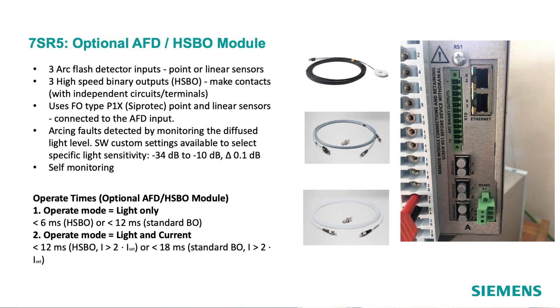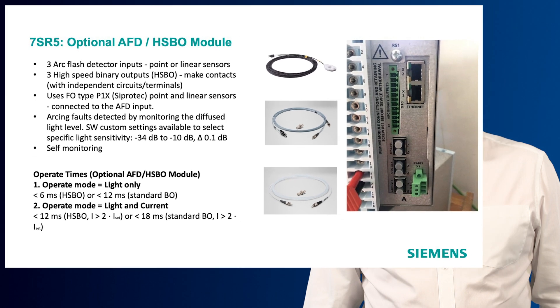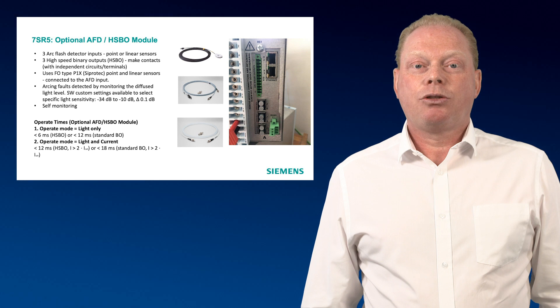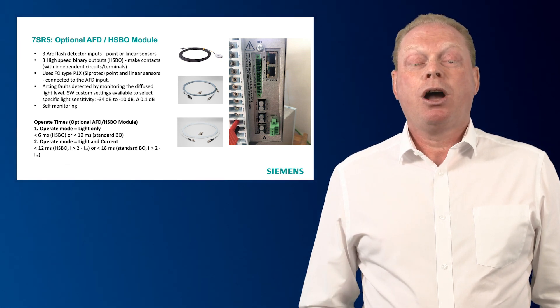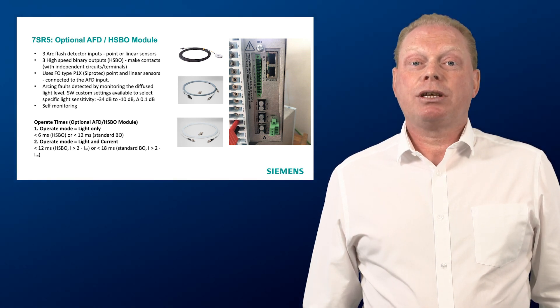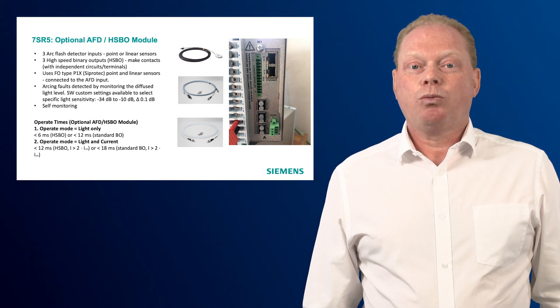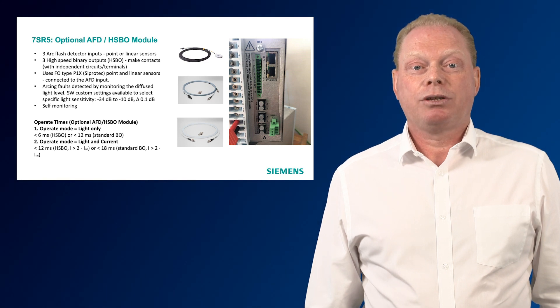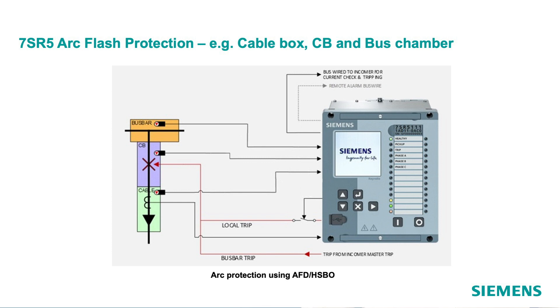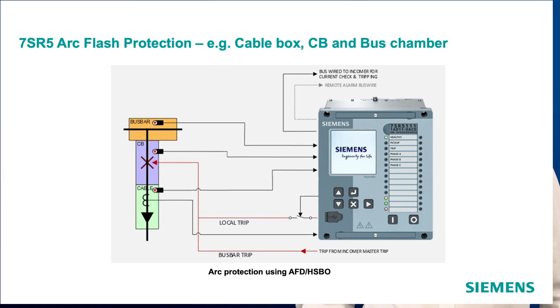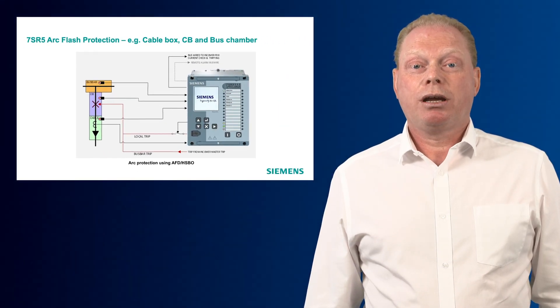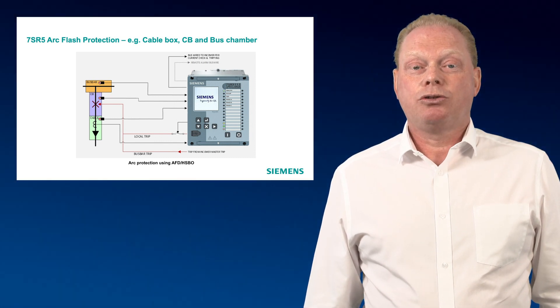There is a trend in distribution substations with air insulated switchgear to minimise the damage of circuit breaker and bus bar faults using arc protection. This solution detects the arc flash light produced by the fault and trips the relevant circuit breakers. The Reyrolle 5 option has three arc sensor inputs and three high-speed binary outputs which can provide operate times of less than six milliseconds. Typically, the arc flash signal is combined with an overcurrent element to avoid unwanted tripping and the 7SR5 Reyrolle 5 can be configured for this. The arc flash sensors need to be ordered separately and can be supplied as point sensors or linear sensors if greater coverage is required. Typically the sensors are placed in the current transformer, circuit breaker and bus bar chambers and the Reyrolle 5 logic configured to trip the correct circuit breaker.